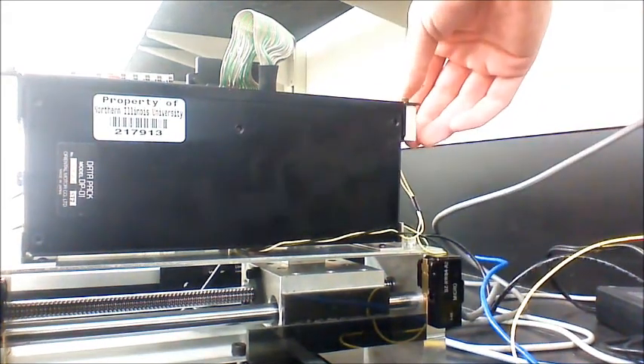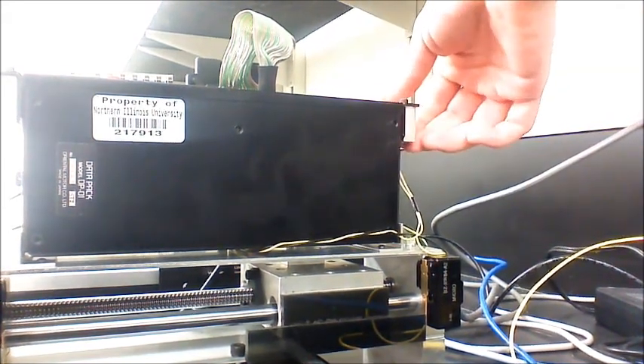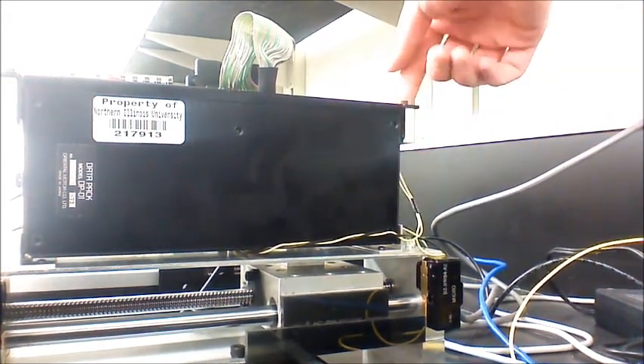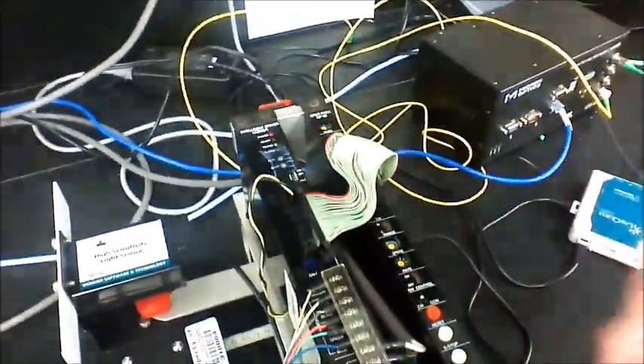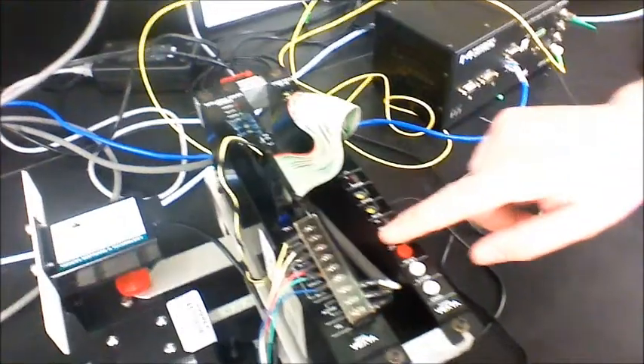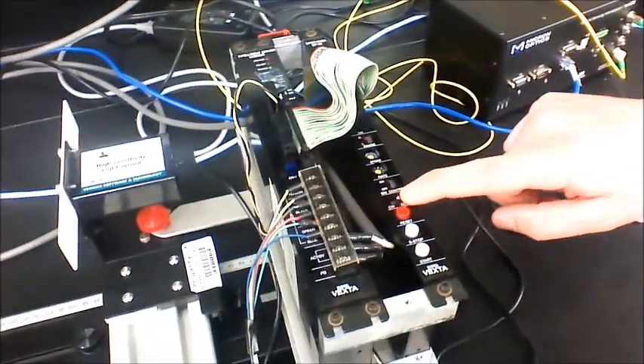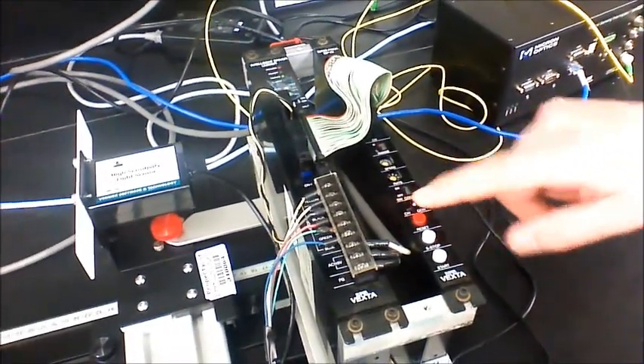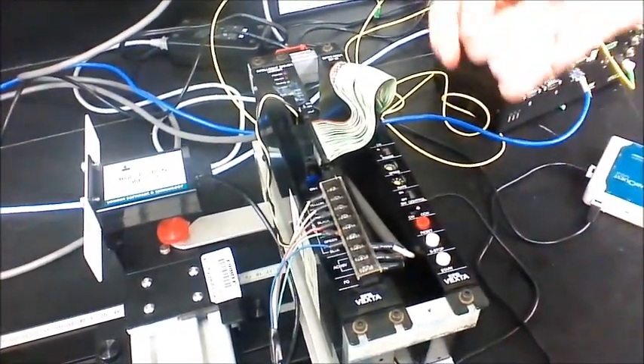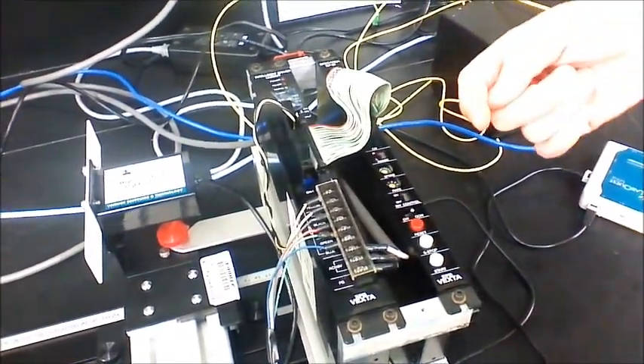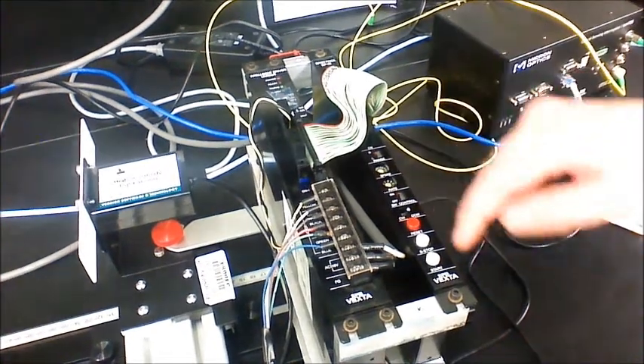When that tab is pressed in order to get the motor to be ready, back up on top here is a nice little red button. Pressing that gets the motor ready. Here is a switch clockwise, counter-clockwise. That changes the direction of which way your detector is going to move.